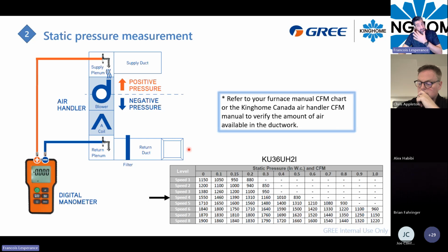So you can refer to your furnace installation booklet, and you will always find this kind of chart in every kind of furnace or air handler. It doesn't matter, the way to measure the static pressure in your ductwork is still the same, even if it's an air handler or a furnace.